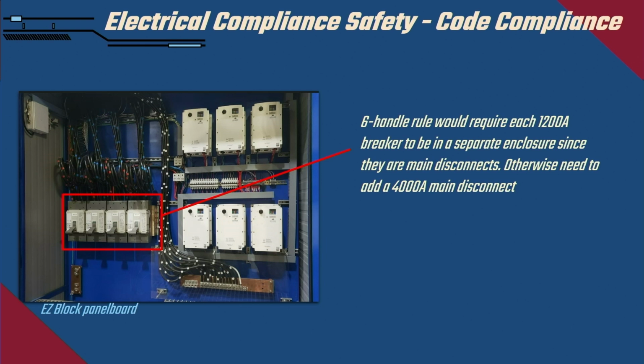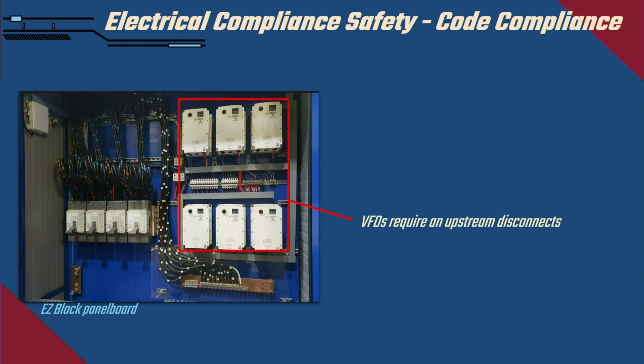So either way, it's a lot of rewiring and a lot of money that you could potentially spend just to make this code compliant. So this particular pod has 6 VFDs. These follow the same error as the PDUs. They're feeding directly to the 1200 amps with no service disconnects on the upstream of those VFDs. You would need to add those as well just to protect those VFDs.